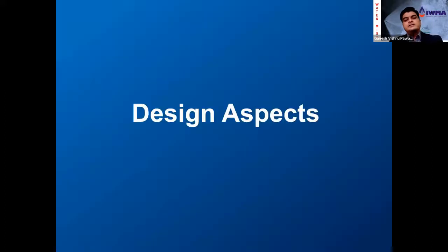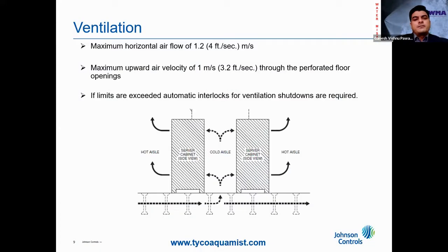So let us consider the design aspects. Ventilation plays a very vital role while designing the system, because ventilation is essential to maintain the optimum operating condition inside the data halls. Our low pressure water mist system is FM approved for a horizontal airflow up to 1.2 meters per second and an upward air velocity up to 1 meter per second. If the ventilation exceeds these parameters, then it is essential to have an automatic interlock so that we can achieve these limitations.